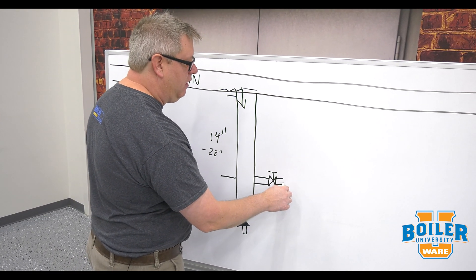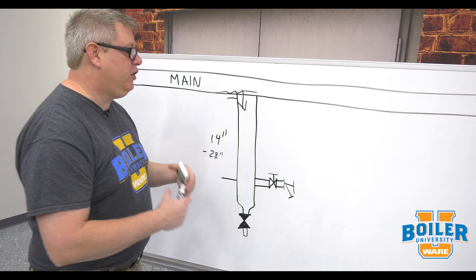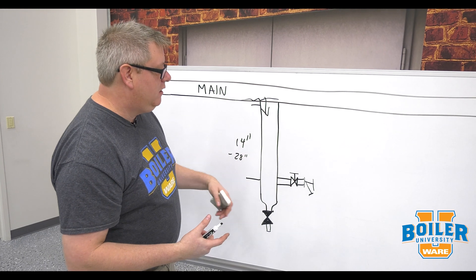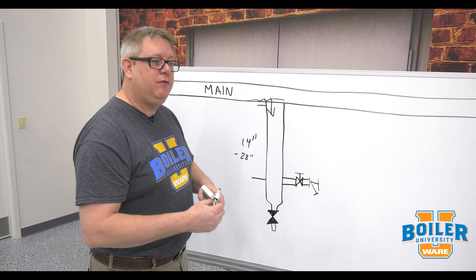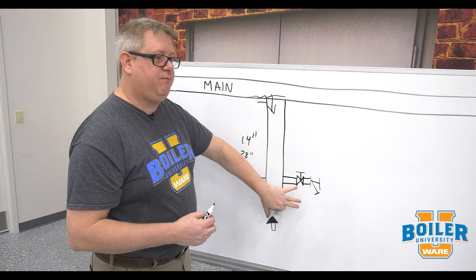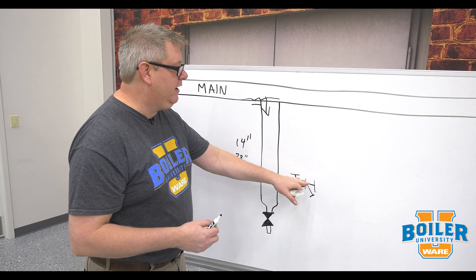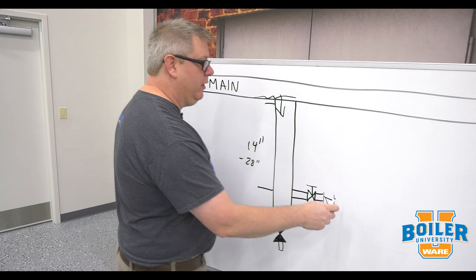After that isolation valve we want to have a strainer. A strainer protects the trap from debris that comes in and some traps have strainers integrated. If you're putting in a new drip leg feel free to use that integrated strainer. If there's an existing strainer I'm never going to take that out regardless of what type trap I'm putting in.